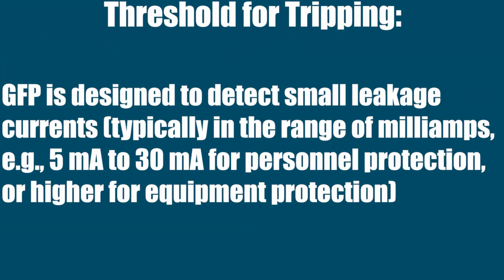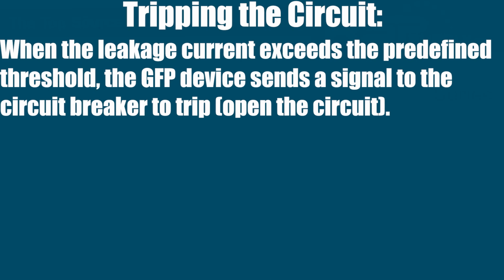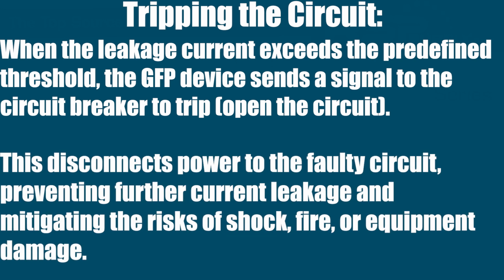There is a threshold for tripping. Ground fault protection is designed to detect small leakage currents, typically in the range of milliamps. For example, something like 5 milliamps to 30 milliamps for personnel protection, or even higher for equipment protection. Then there's tripping the circuit. When the leakage current exceeds the predefined threshold, the GFP device sends a signal to the circuit breaker to trip, opening the circuit. This disconnects power to the faulty circuit and prevents further current leakage, which reduces the risks of shock or fire or equipment damage.